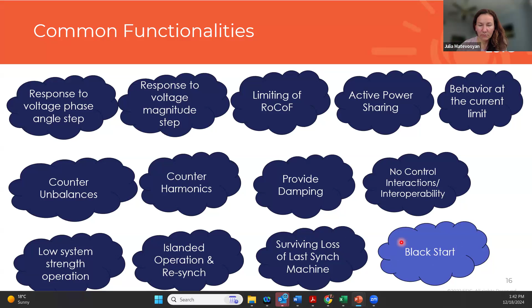Other requirements include countering imbalances and harmonics, providing damping, not causing additional control interactions, being interoperable, low system strength operation, islanded operation, and the ability to resynchronize back to grid connected operation, surviving loss of the last synchronous machine. This is tested through simulation. In the majority of requirements, it's not expected that a grid forming resource supports the grid without any synchronous machines, but the test is used to prove that grid forming capability is there. Black start capability I colored differently because it's not everywhere, and where it is mentioned, it's defined as an advanced capability requiring design consideration, like a special requirement that's usually paid for.